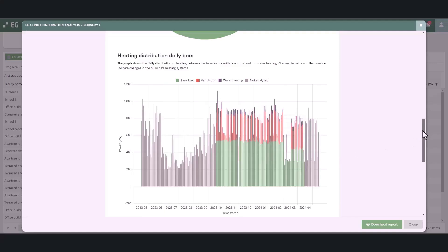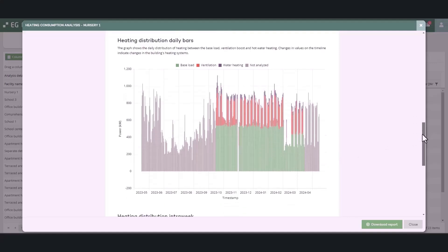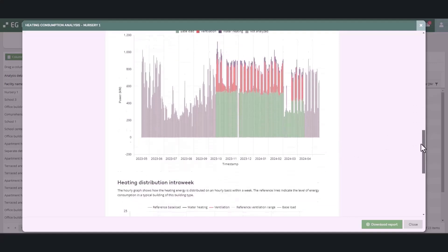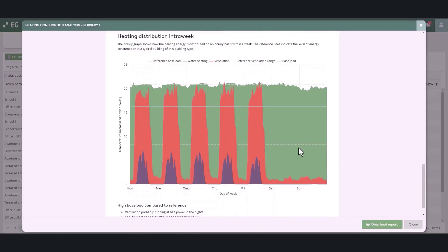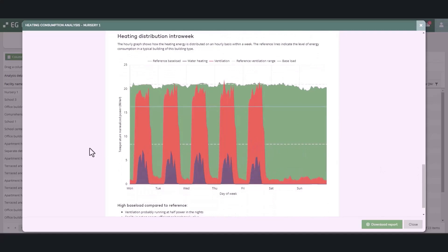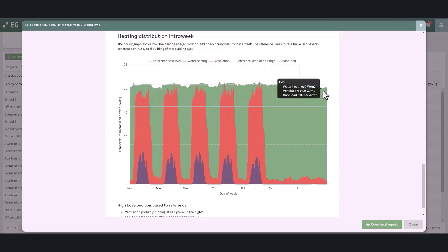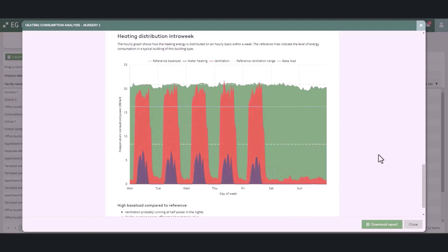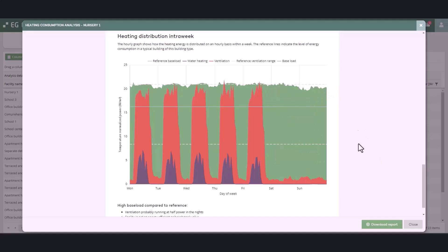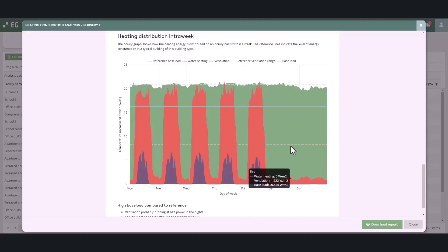The heating distribution intraweek graph shows how the heating energy is distributed on an hourly basis within a week on average. The reference lines indicate the level of energy consumption in a typical building of the same building type. There are two reference lines for ventilation which indicate the range in which the heating energy consumption of ventilation is typically when the air volumes are at a normal level typical for the facility type.